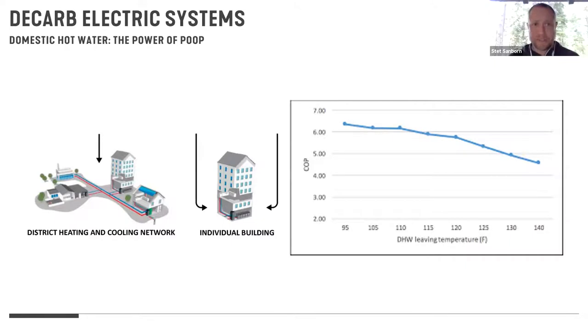And so this system that we're working with, doing sewage heat extraction for domestic hot water production, where we want to make 140 degree water to store, even then we're seeing a COP of 4.5. And when we were doing all the parametric modeling as part of the ASHRAE multifamily energy design or zero energy design guide, for climates 4, 5, 6, and 7, the system came out on top from an efficiency standpoint versus all the other ones.